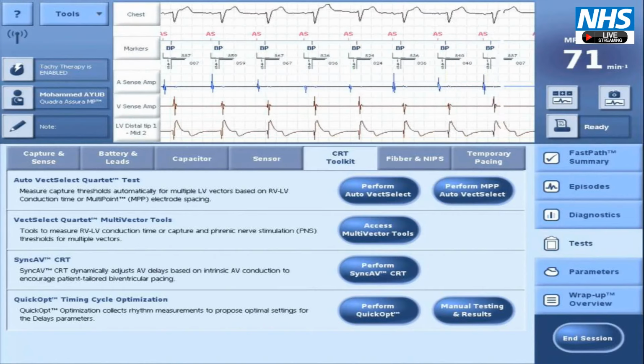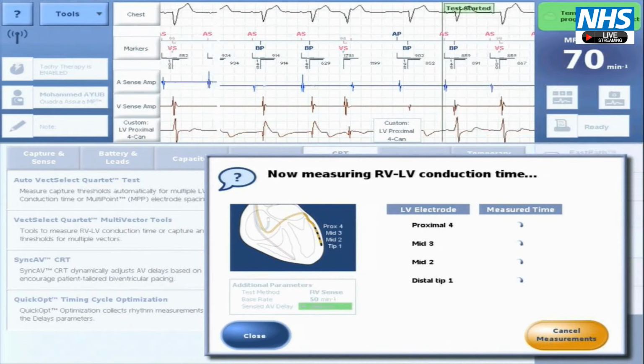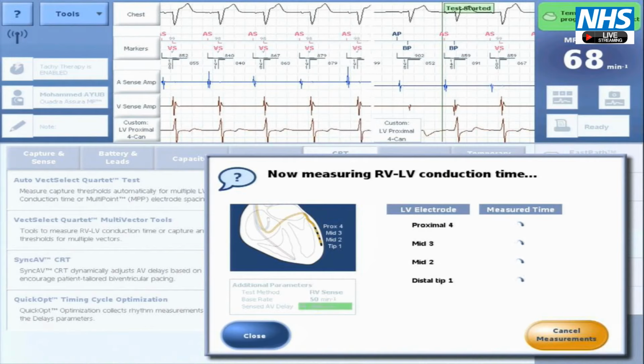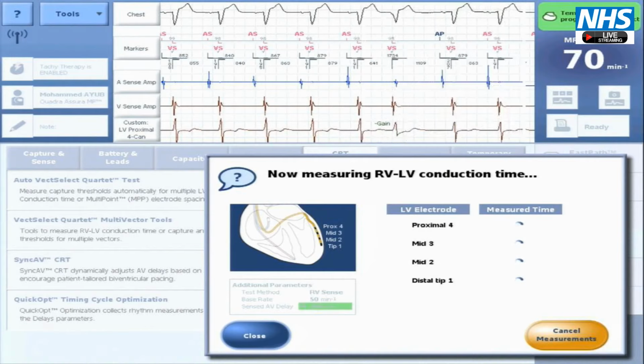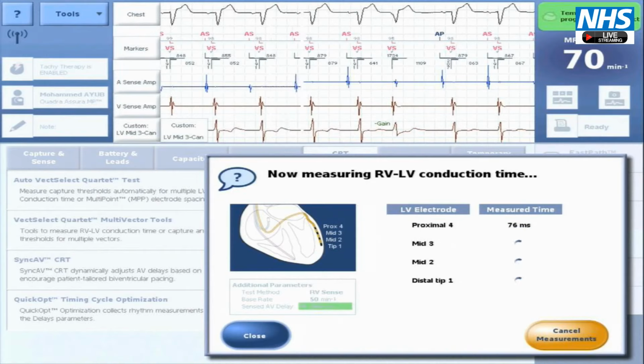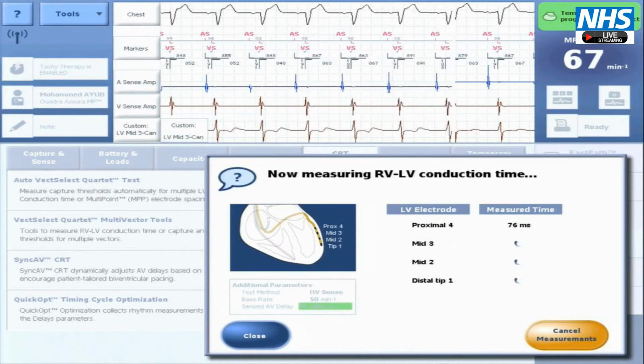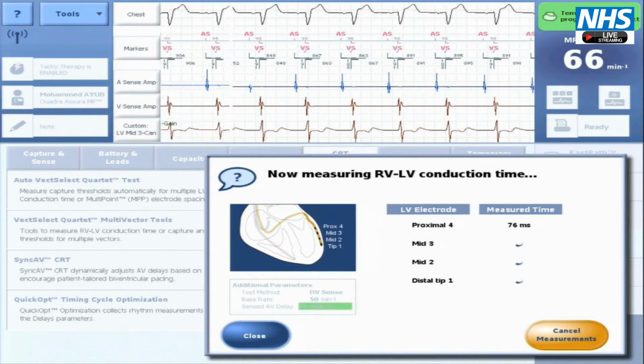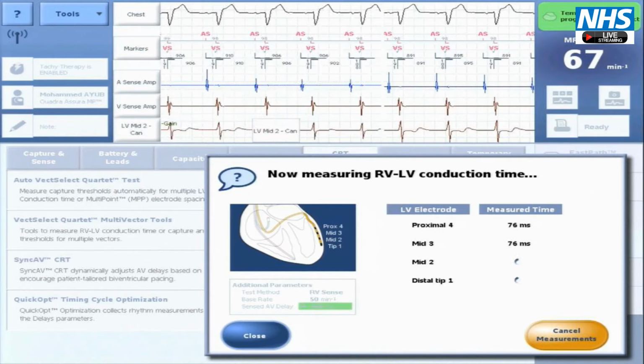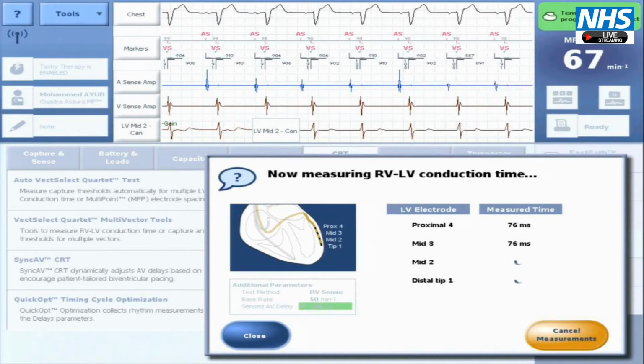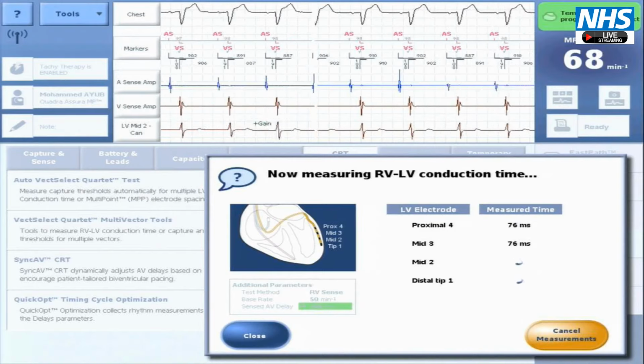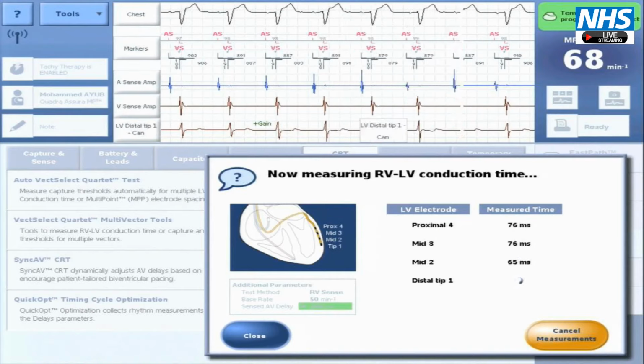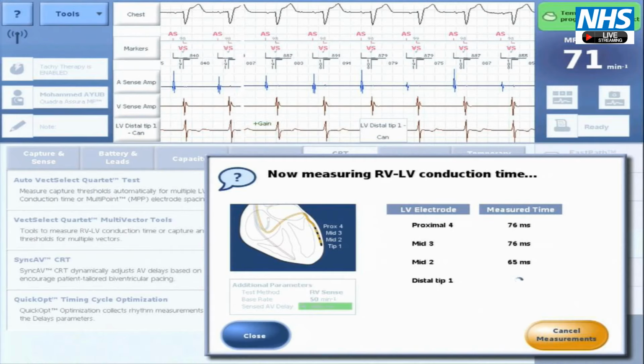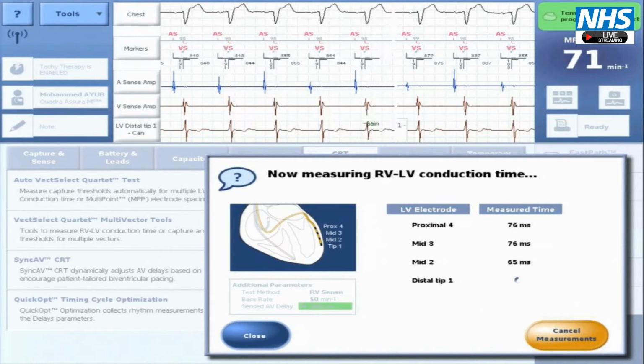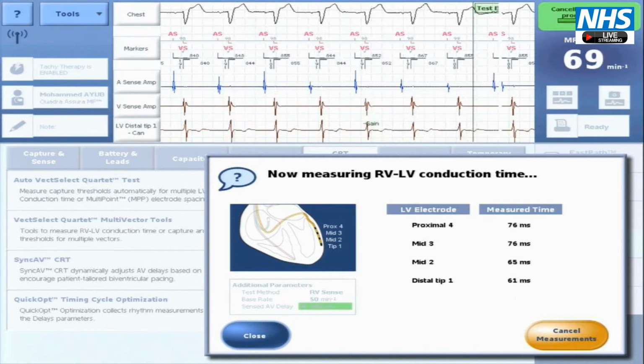So for those of you that aren't sure, this is the time it takes to activate the LV lead after first activation of the RV lead, i.e. the electrical delay of the LV lead. We would typically want this to be a value in the final third of the QRS duration, as there is an evidence base that suggests a long QLV is a good marker for patient response. We should be mindful, though, of not pacing an LV scar. This can be pro-arrhythmic and may be characterised by very late QLV measurements or a very wide LV paced QRS duration. If possible, a cardiac MRI scan to determine optimal lead positioning or areas of scar would be very useful in the ideal world.